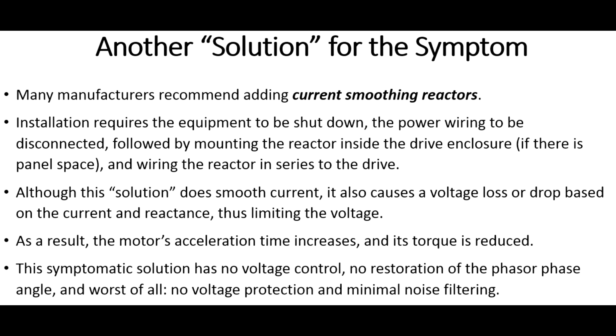However, to install these line reactors, you have to shut the machine off, stop it from operating, disconnect the power feed to the drive, and find a place to mount these line reactors in the panel. If there isn't a spot, physically add another enclosure to house them, and then connect them in series with the power wiring feeding the drive.